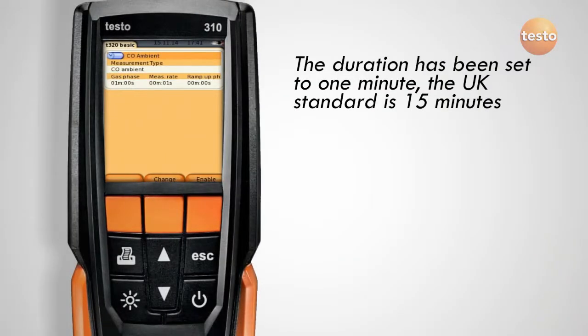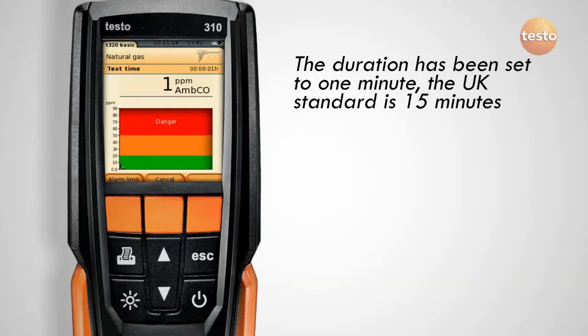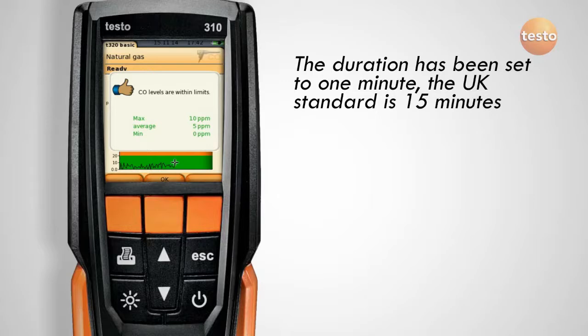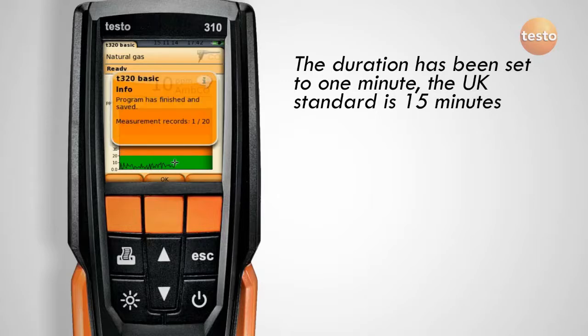The 320B logs the measured CO to memory every second, or less frequently if you prefer. At the same time, it charts the CO level against preset warning and alarm limits. If the CO goes above the alarm limit, the analyzer gives an audible alarm, and when the test terminates, it will warn you to switch off the appliances and open the windows.